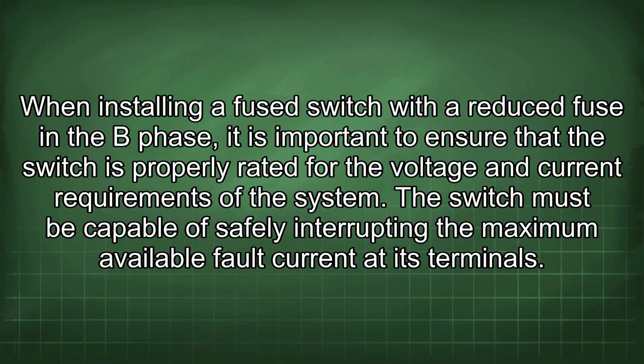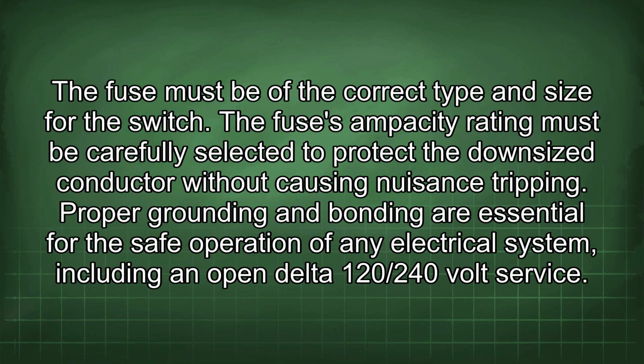When installing a fused switch with a reduced fuse in the B phase, it is important to ensure that the switch is properly rated for the voltage and current requirements of the system. The switch must be capable of safely interrupting the maximum available fault current at its terminals. The fuse must be of the correct type and size for the switch. The fuse's ampacity rating must be carefully selected to protect the downsized conductor without causing nuisance tripping.